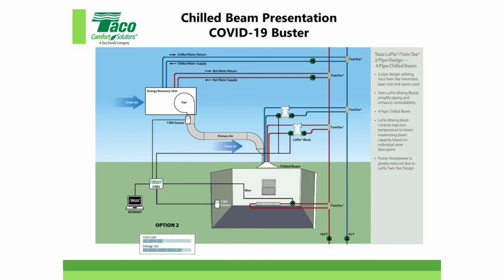Here's our controllers, right? We actually have a controller for each zone. They can all tie together. Here's our primary air coming back. We have one hot water going around for the baseboard, right? Pulling off. One hot water with the LoFlo mixing block for the heating for the chilled beam, and then a cold water mixing here, right?